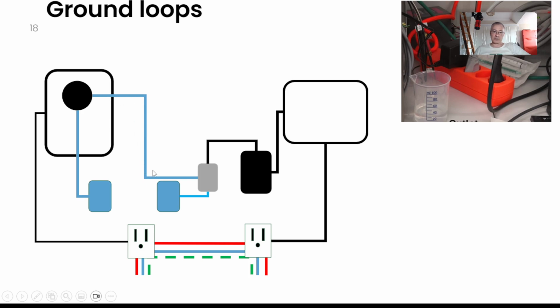Most electrical and electronic engineers don't think about this too much because they're used to conductivity through wires, and they can't imagine conductivity through solution. I don't want to generalize too much, but it is a bit of a strange concept. But in fact, you do have electrical contact through these two systems. I can absolutely understand the argument that there shouldn't be electrical contact because this pump head should be very isolated. But if it's not, then this theory could be the case. I'm not defending it, I'm just giving it out as one of the options.